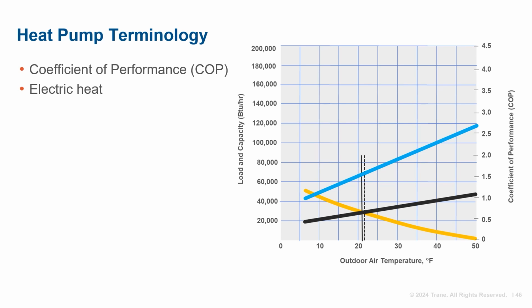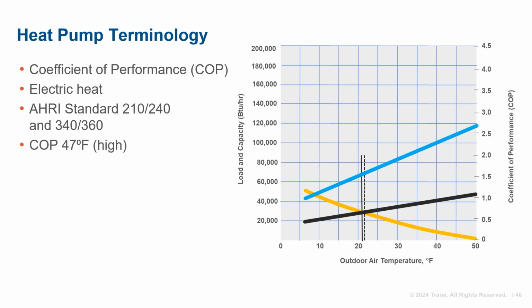Let's review this in more detail. The attached image represents the difference in the building load as a function of outdoor air temperature across the horizontal axis versus a typical unit's capacity as shown on the vertical axis. The blue line represents the COP as a function of outdoor air temperature, while the black line represents capacity. As ambient conditions change, so does the capacity. Keep in mind that heat pump efficiencies are tested per AHRI 210/240 for equipment up to 65 MBH, and 340/360 for units up to 300 MBH. The standard COP test conditions are 47 degrees Fahrenheit for high and 17 degrees Fahrenheit for low.